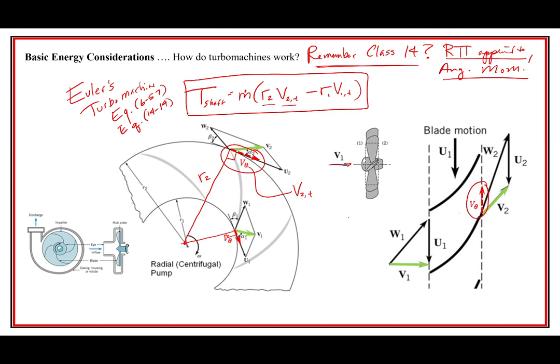A key thing we need to focus on to find these velocities is velocity triangles - they're turbomachinery's best friend and a necessary part of working with any turbomachine. You have to deal with velocity triangles because this thing is moving, so it has a velocity due to rotation - the angular velocity times the radius. There's also a relative velocity, which is the velocity that the blade sees.